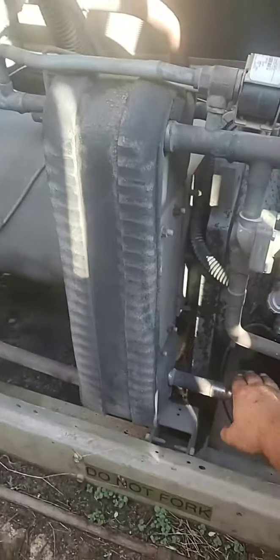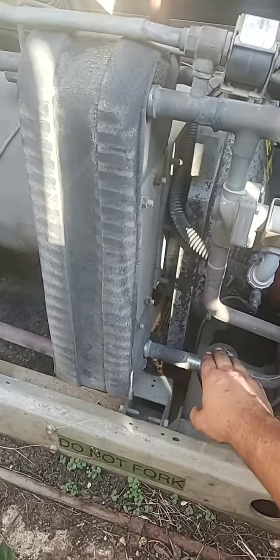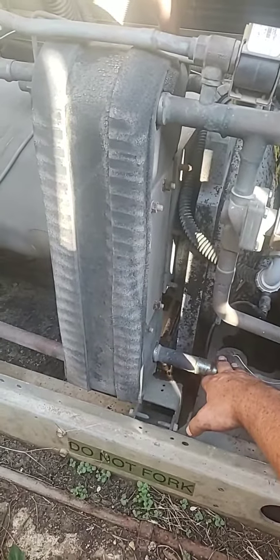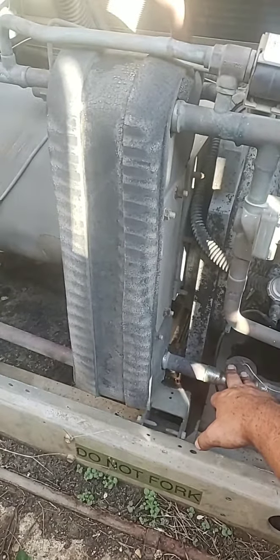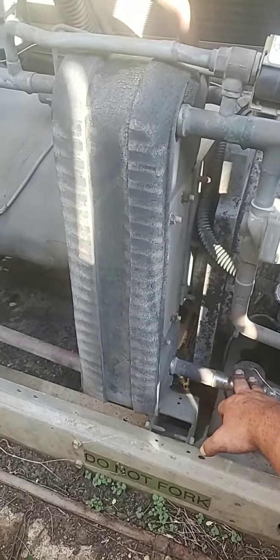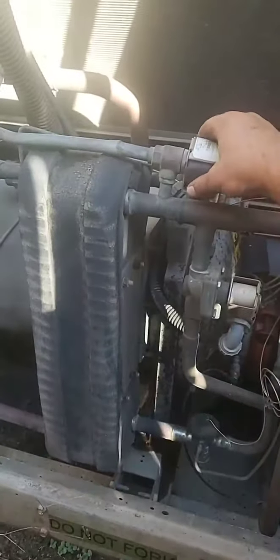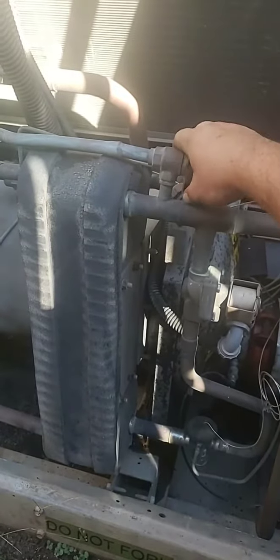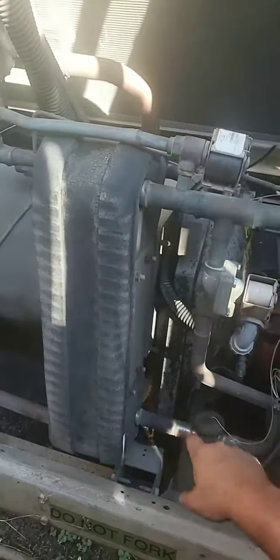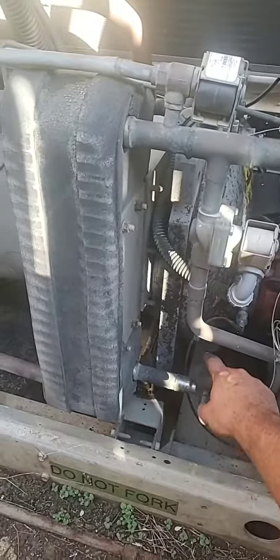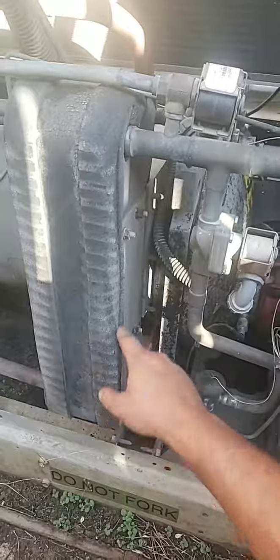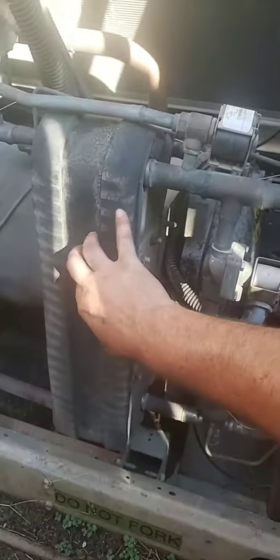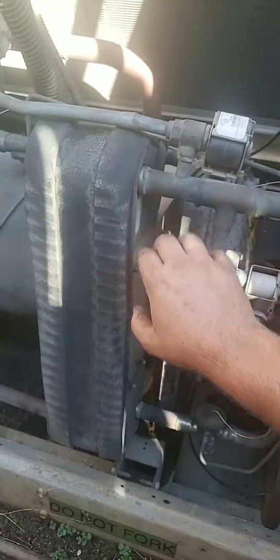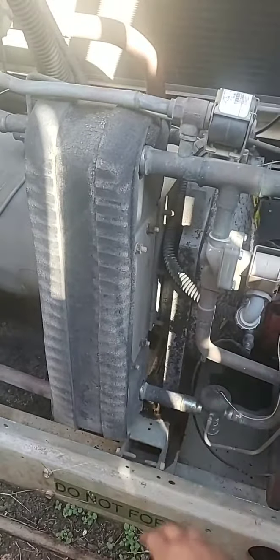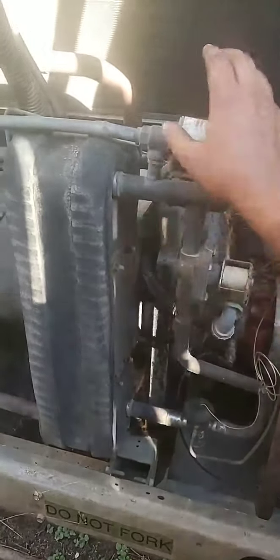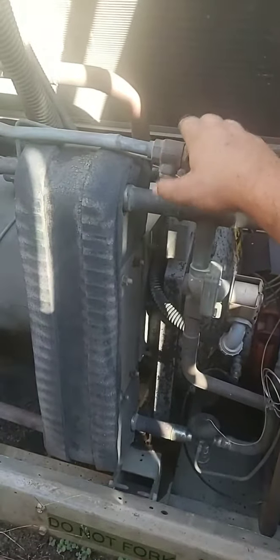So this TXV, while it is doing the economizer, does play a very minor role in helping the motor regulate temperature. But this valve up here, as I said earlier, its main job is to actually control motor temp. This TXV by itself is not sufficient in how much it's flowing through after it cools this refrigerant or the liquid line. It is not sufficient in keeping that motor cool on its own. This valve has to continue to be working.